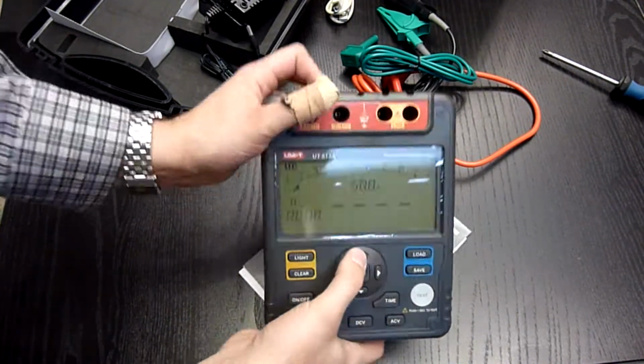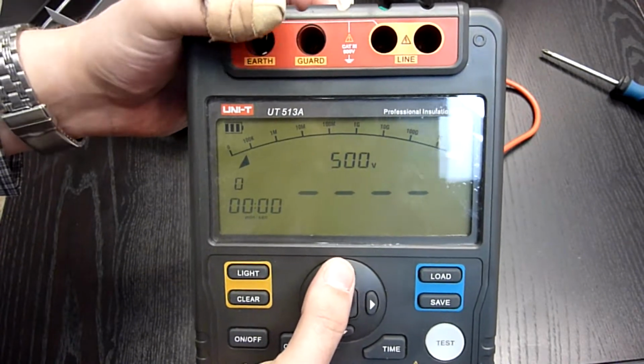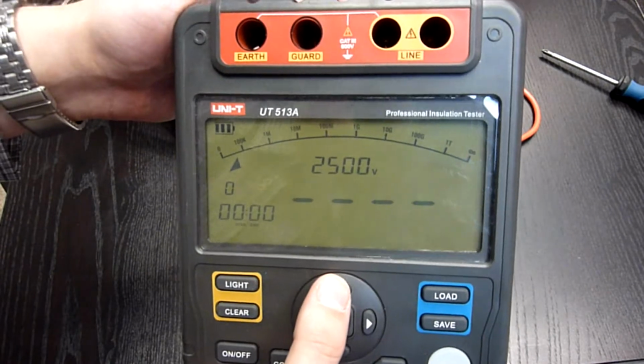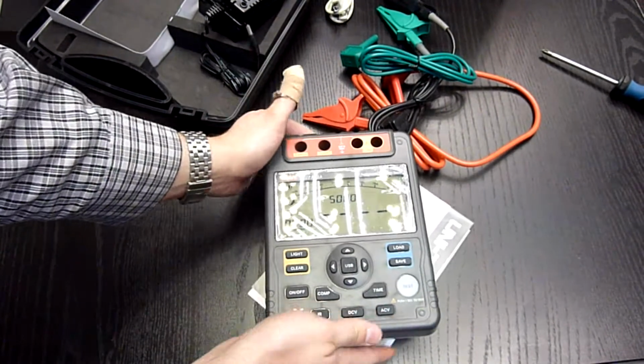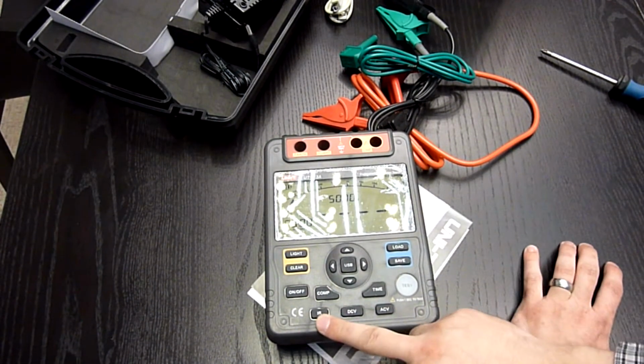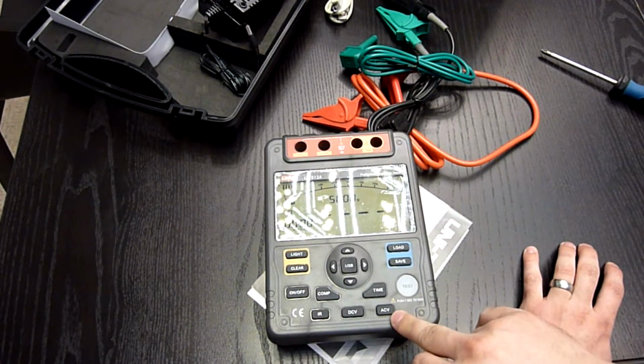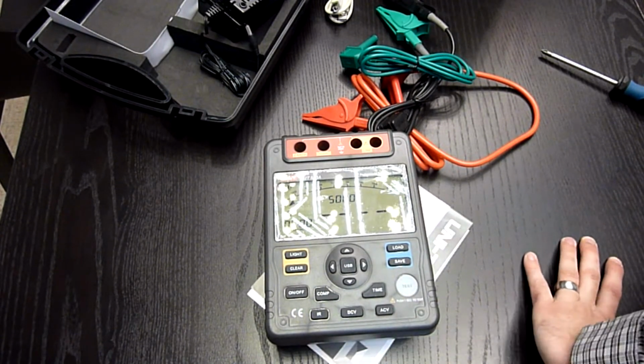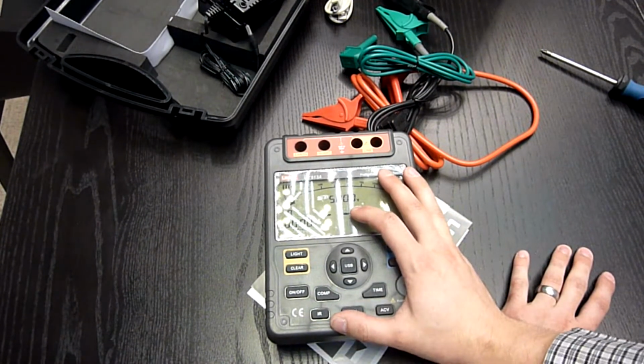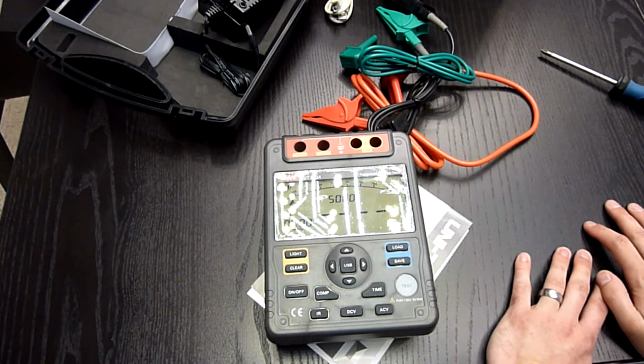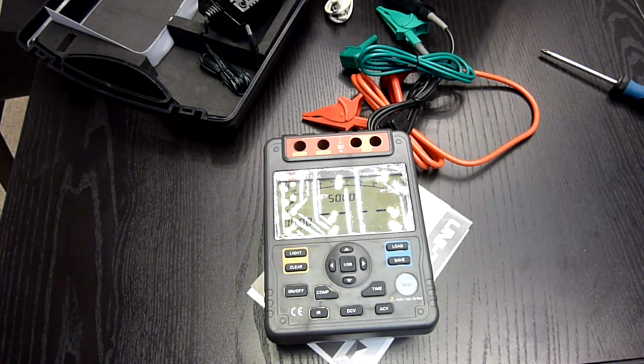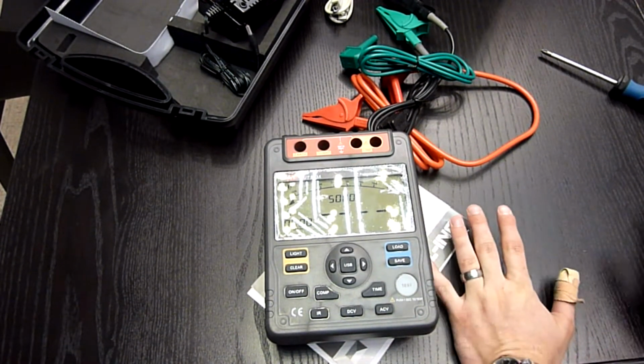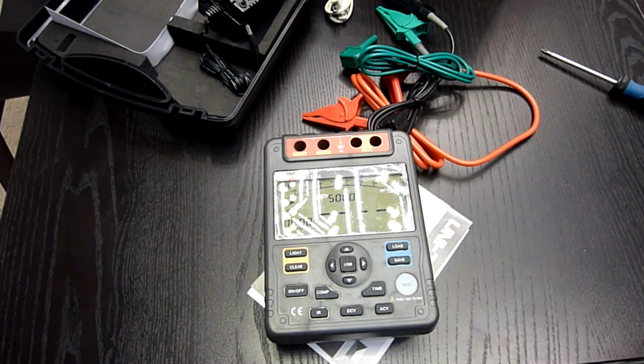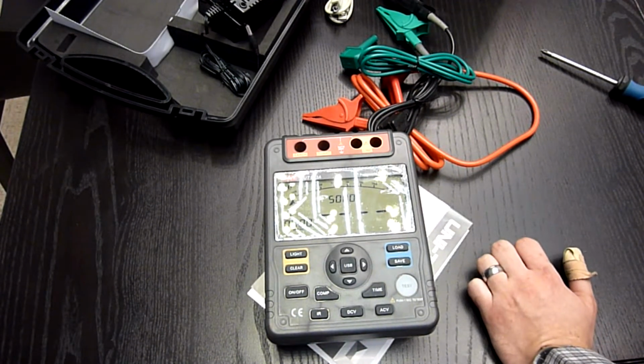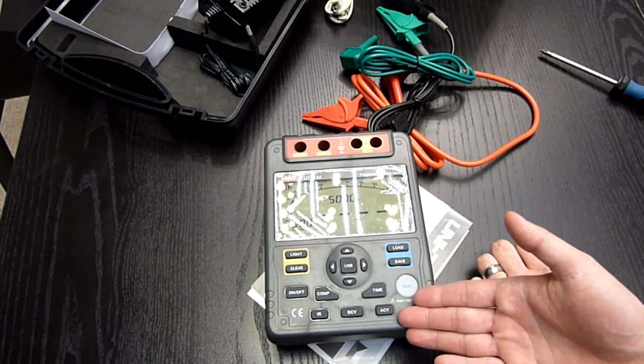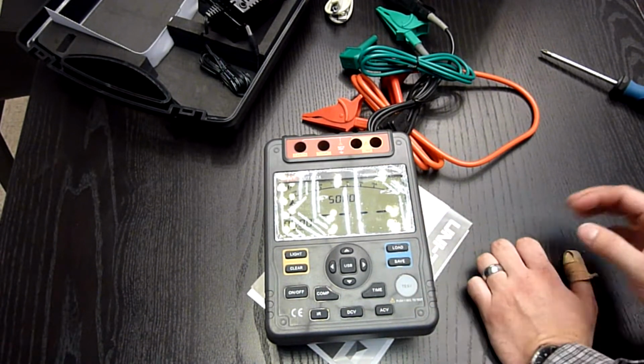So we can choose between testing voltages of 500 volts, 1000, 2500 volts and 5000 volts, 5 kilovolts. Besides the insulation resistance, the meter can also measure DC voltage and AC voltage, but only up to 600 volts. Regarding this insulation resistance, the accuracy is kind of normal for these devices. It's within 3% plus 5 digits. All this is auto range. The resistance value is shown automatically, you don't need to switch anything. Also, there is memory inside for 18 values, which you can load, save, then read through PC.